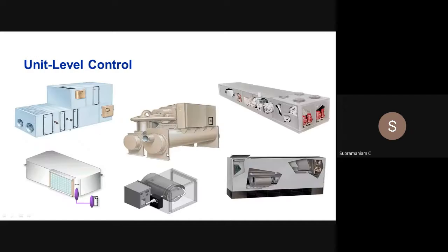So that is the same for all this kind of equipment. Water cooled chiller is this one. Your package unit, rooftop package unit is this one. Fan coil unit, VAV box. Your heat pump package unit, your air handling unit with factory mounted control, field mounted control. See, AHUs are now already available with factory mounted control. All the controls you can mount in the factory. When the customer gets everything, they just have to give power and do control wiring, and it will start working on its own. So that is your unit level control.